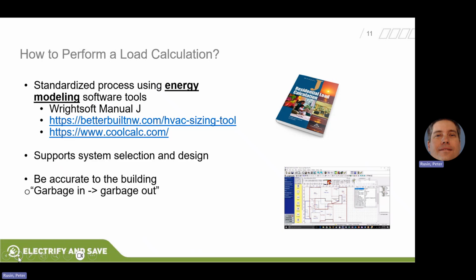It helps support the system selection and design, but the bottom line is garbage in, garbage out. Use your rules of thumb for some sanity checks. If it says you're in climate zone 7 with a 5,000 square foot home, and it's telling you to put in 24,000 BTUs, that doesn't check out. Use your knowledge in the field.